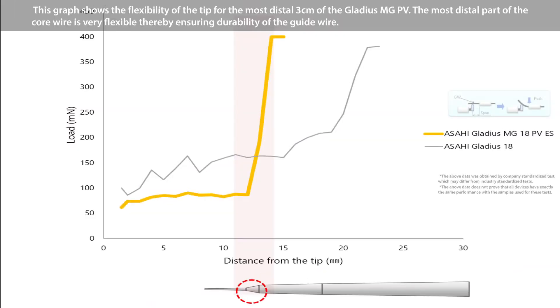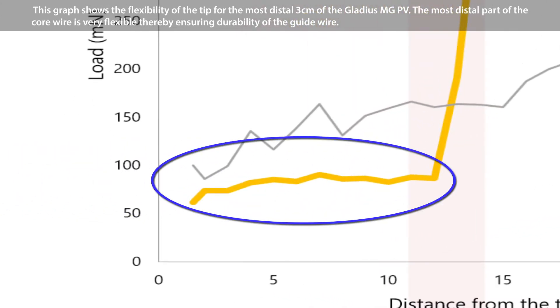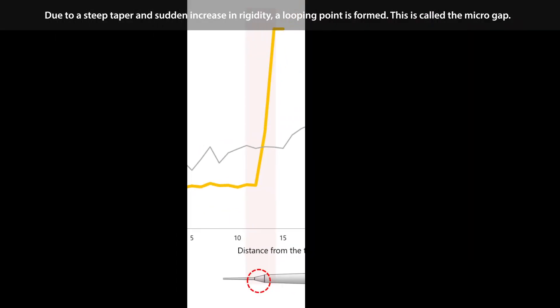This graph shows the flexibility of the tip for the most distal 3 centimeters of the Gladius MG PV. The most distal part of the core wire is very flexible, thereby ensuring durability of the guide wire. Due to a steep taper and sudden increase in rigidity, a looping point is formed.